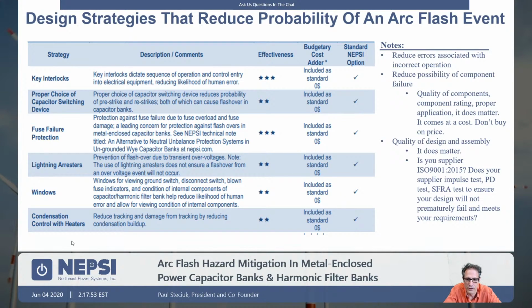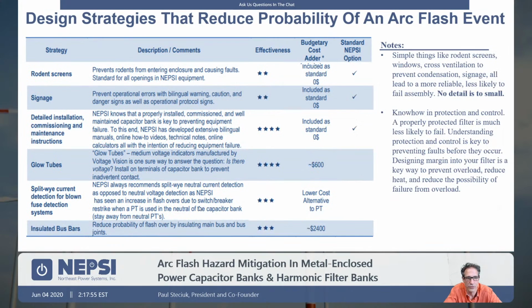We also incidentally put IR windows in our equipment to allow for infrared scanning. Also prevents people from wanting to open that door while it's energized. We protect against rodents. We have a significant amount of signage. If you understand the equipment, if you understand what's behind the door, you're less likely to open the door.